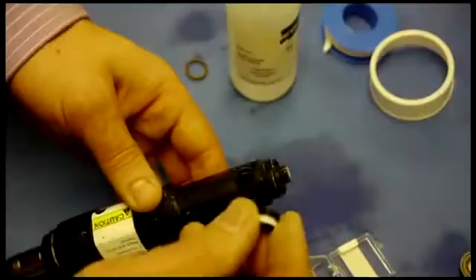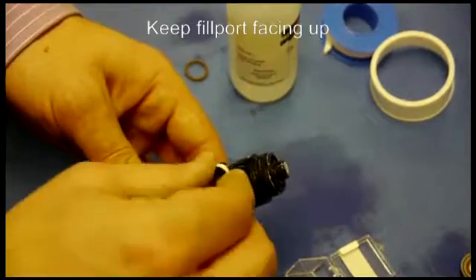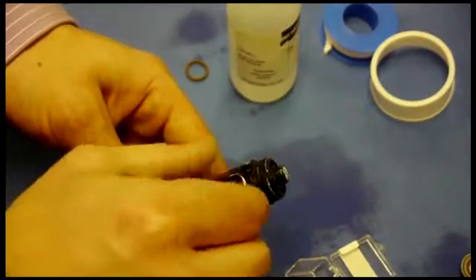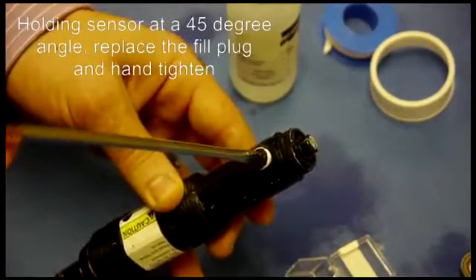Now grab the fill plug, which I made sure there was enough pipe tape remaining on. Keep the sensor at about 45 degrees so the solution does not spill out, and begin tightening.